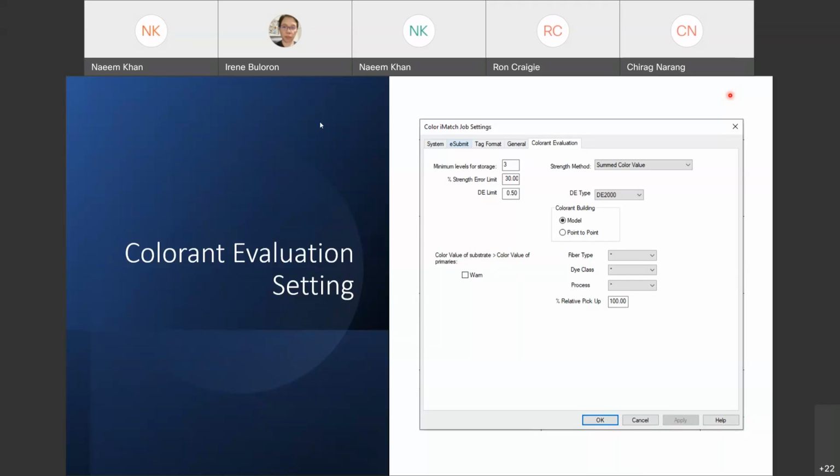If the difference is more than 30%, which is the limit we have defined, the software will not accept that sample. If it is less than 30%, it will accept. But it depends on the nature of our dye stuff, which dye stuff we are working with, and based on that we can increase or decrease this limit. Normally, as a SOP, we use 30% and we recommend 30%.